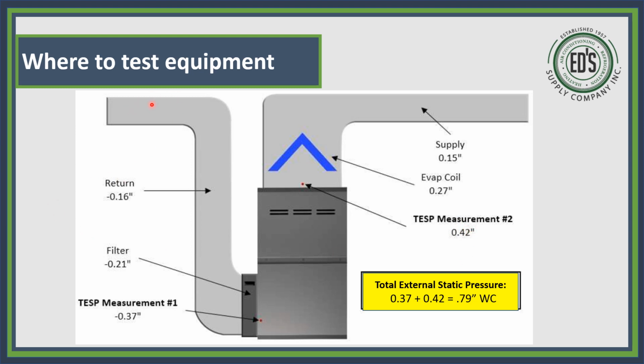Now, over here on the return, you put a probe in here, and you got 0.16, which is great for this. And then you come down here to your filter, and you have a 0.21 in the filter area, but your total return is 0.37. That's really high for a return. So that lets me know we have issues right here because we've just choked down our return.